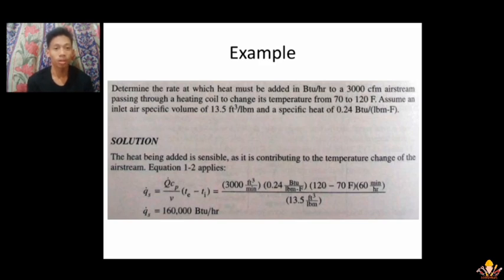For the example, determine the rate at which heat must be added in BTU per hour to a 3,000 cubic feet per minute airstream passing through a heating coil to change its temperature from 70 to 120 Fahrenheit. Assume an inlet air specific volume of 13.5 cubic feet per pound mass and a specific heat of 0.24 BTU per pound mass Fahrenheit. So for the solution, the heat being added is sensible, as it is contributing to the temperature change of the airstream.